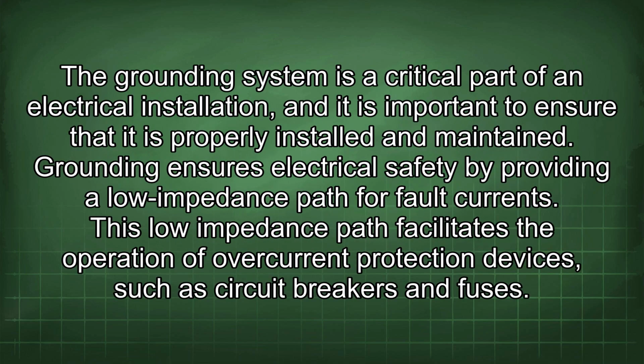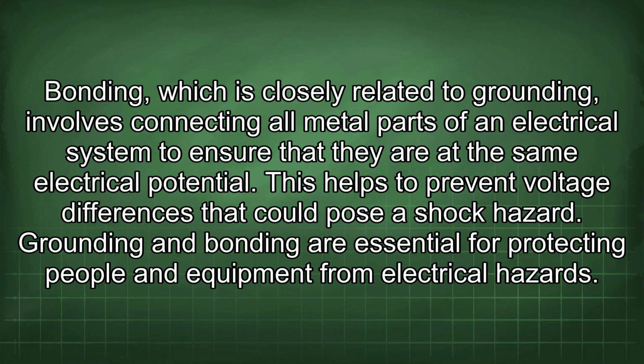The grounding system is a critical part of an electrical installation, and it is important to ensure that it is properly installed and maintained. Grounding ensures electrical safety by providing a low impedance path for fault currents. This low impedance path facilitates the operation of overcurrent protection devices such as circuit breakers and fuses. Bonding, which is closely related to grounding, involves connecting all metal parts of an electrical system to ensure that they are at the same electrical potential. This helps to prevent voltage differences that could pose a shock hazard. Grounding and bonding are essential for protecting people and equipment from electrical hazards.